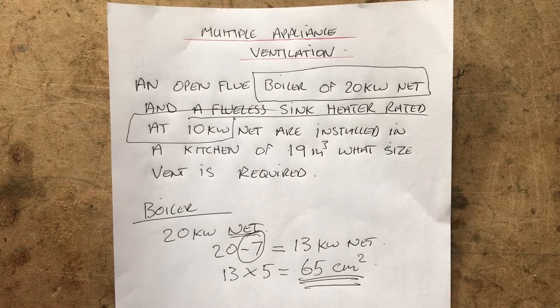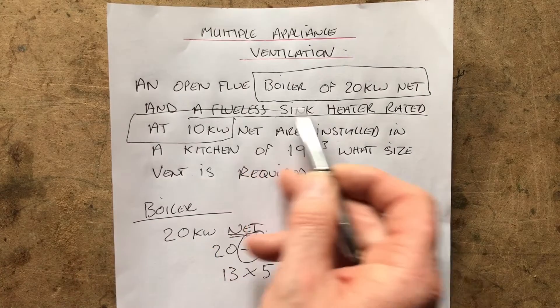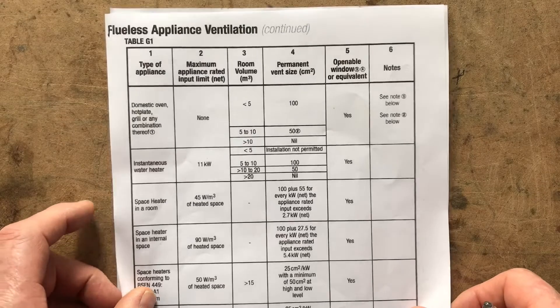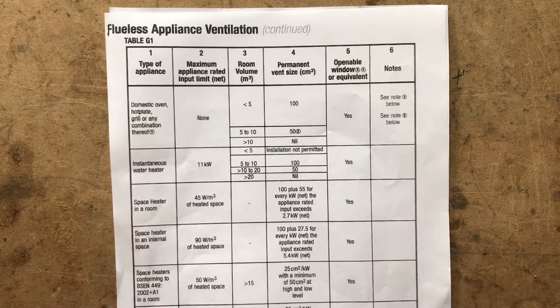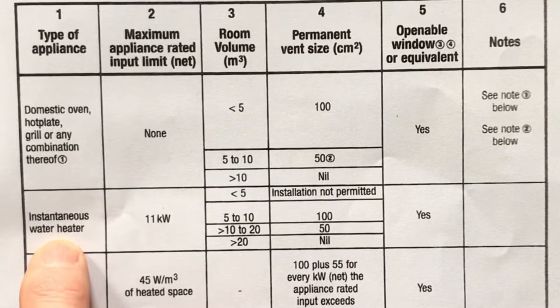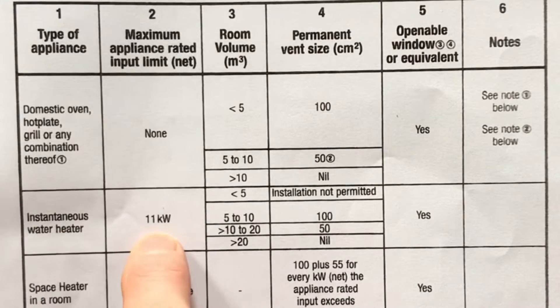Now it also says we have a sink heater — it's flueless. You have 10 seconds to figure out where you would find the ventilation requirements for this flueless water heater. We need to use our chart. So we go to our water heater — there's our flueless water heater. It says it's rated at 10 kilowatts and we can go up to 11, so we know we can use it.